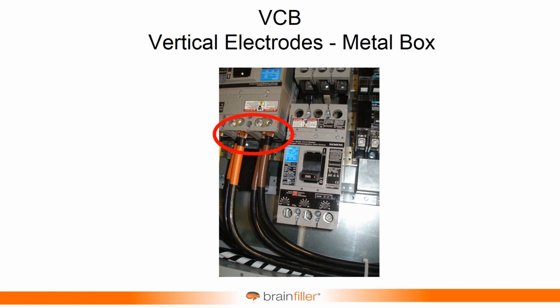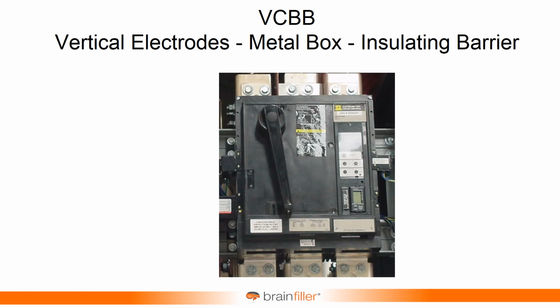Then we have the vertical electrodes in the metal box with an insulating barrier. And it might be something like this. If an arc flash occurs, let's say, up ahead of this breaker, and the energy runs towards the breaker, it hits the insulating properties, and it may behave more like a VCBB type of a configuration.